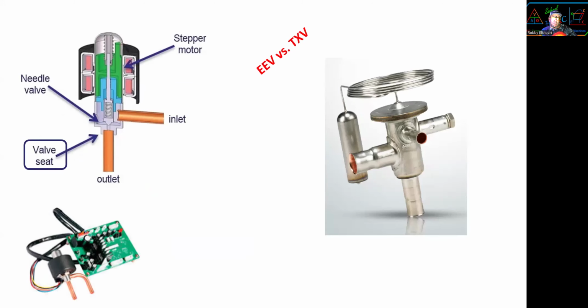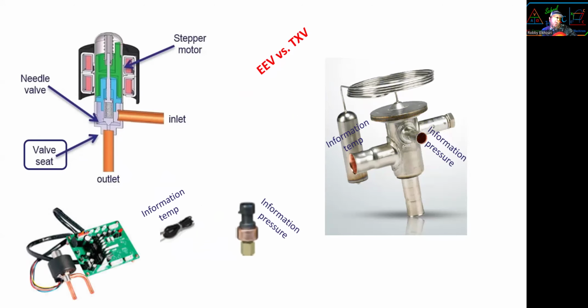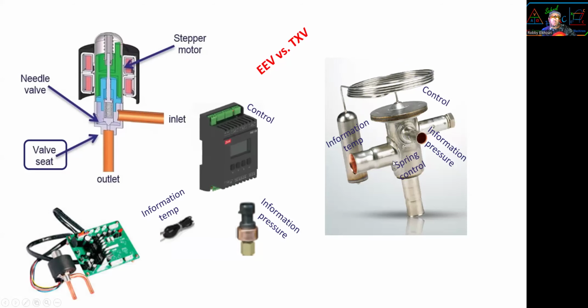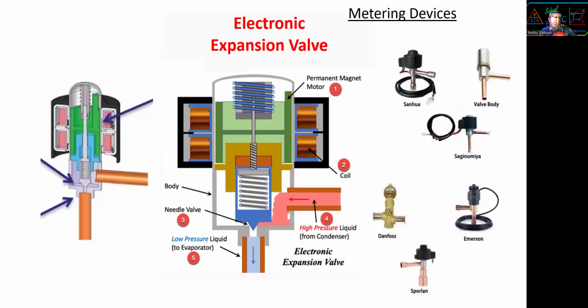Electronic expansion valve versus thermostatic. They both have information, right? The sensing bulb is the information for the temperature. Information is a temperature probe. The pressure transducer is the information for the electronic valve. The external equalizer, I guess, suction pressure is the information. And we have a spring as the control, and a control module. The motor is another control also. And they both have a needle.